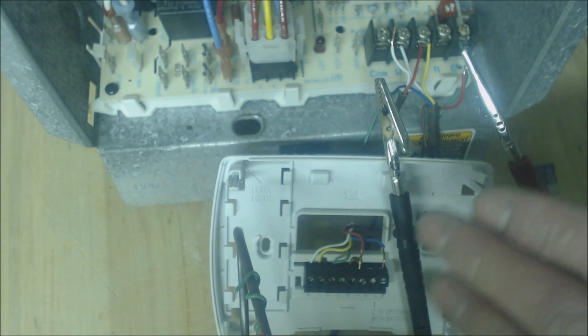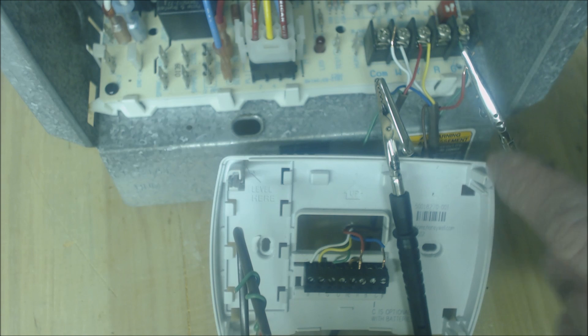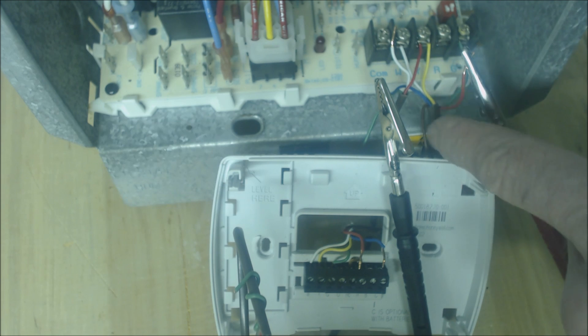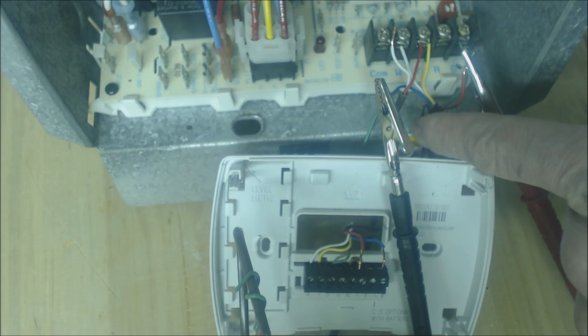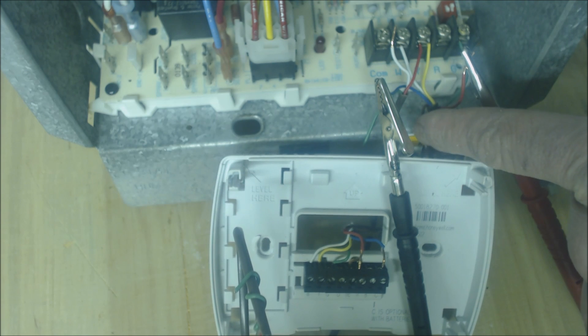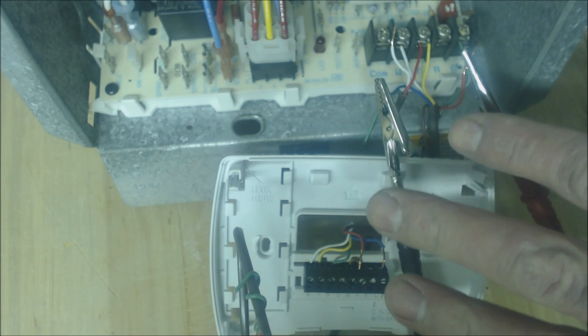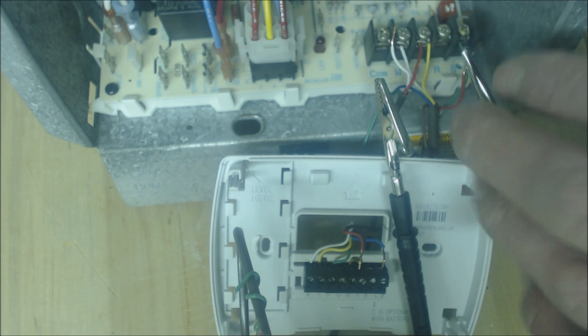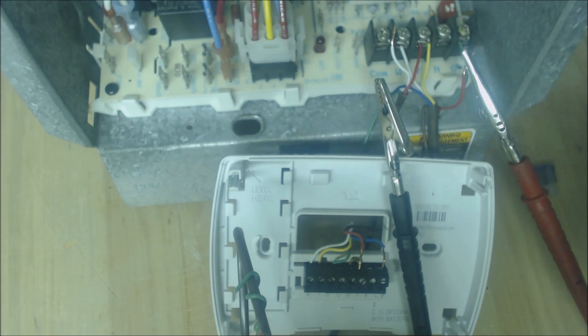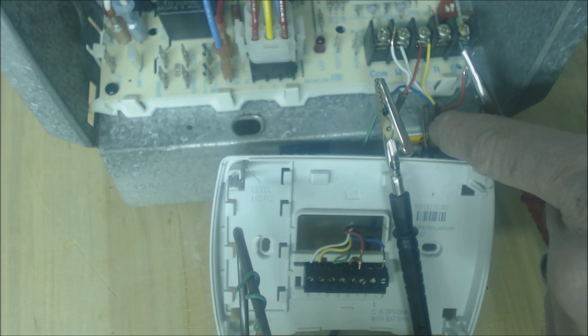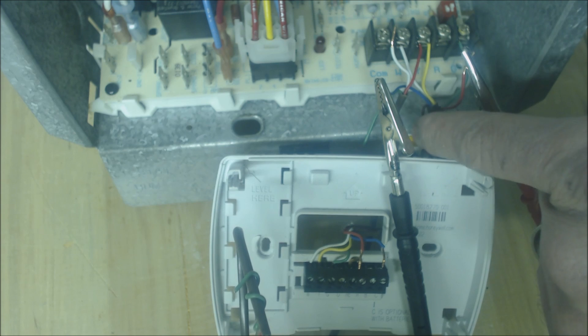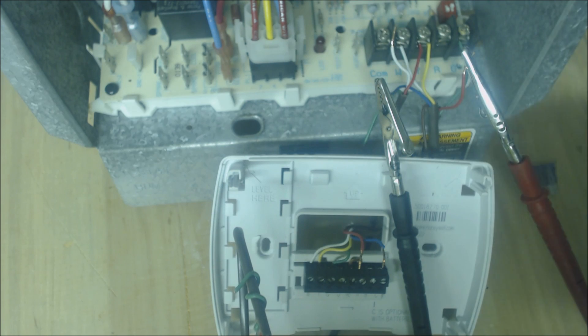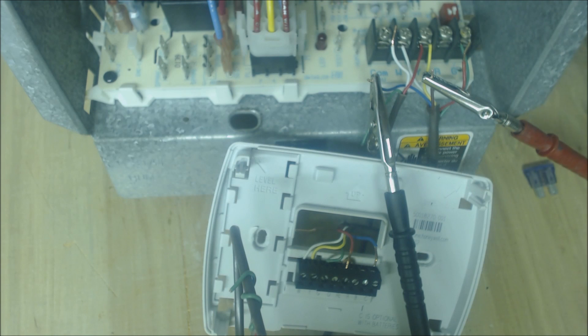Normally what you would do is you would either run a new thermostat wire or you would use an additional wire that's not being used. Anytime I install a system and it needs five wires, I'll run six wires. If it needs two wires, I'll run three wires. You always want to run additional 18 gauge wires for your thermostats just in case you need them later, even for an instance like this.